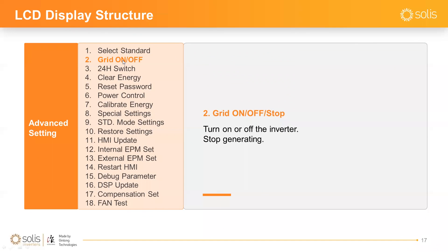Grid On/Off has three options: On turns the inverter on; Off opens the AC relays, physically disconnecting the inverter from the grid; Stop stops generation but keeps the AC relay closed. That is the key difference between Grid Off and Grid Stop.